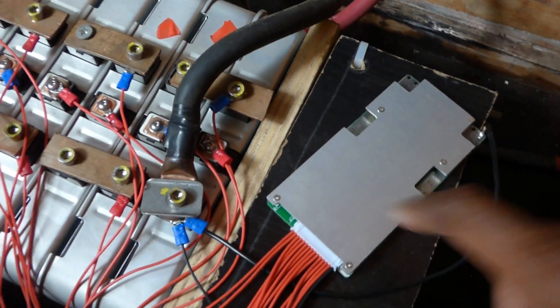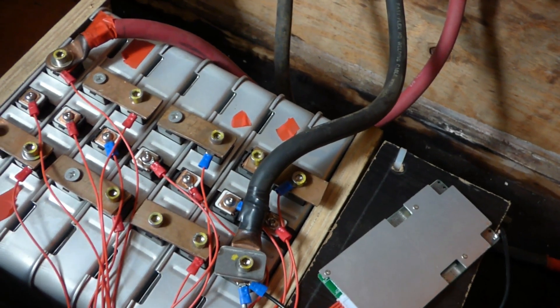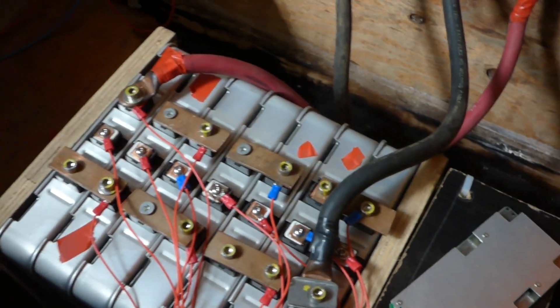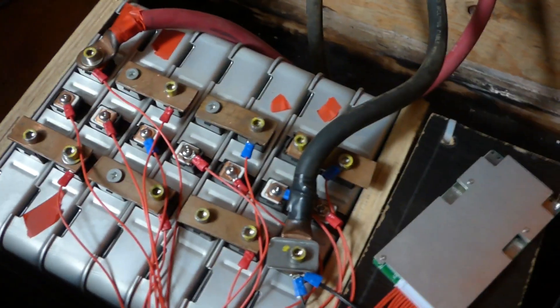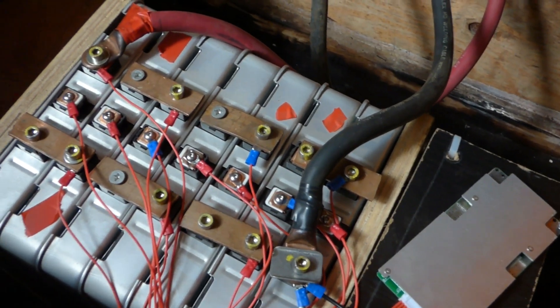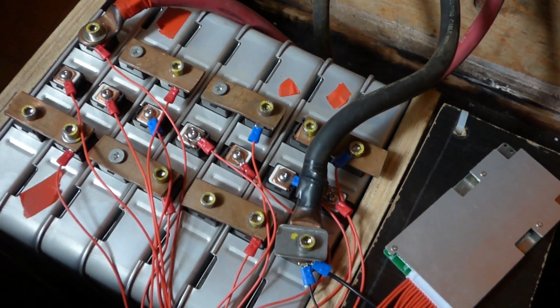Here is our BMS, and our batteries are pretty close in voltage. There's a difference. You have anything from 3.99 for each cell, and the highest is 4.03, which is much better than what we had before.